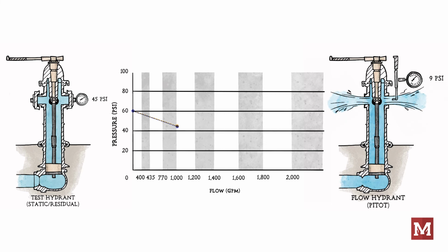Our original curve, we would have estimated fire flow to be about 1,650 GPM. But now, even with a mismeasured residual pressure, our fire flow estimate becomes 1,710 GPM, or just being off by 3.6%. So because we flowed more water, our confidence in our results grows dramatically. Essentially, the real supply that we're going to be able to get out of those hydrants from the fire department is going to be much closer to our test results when we flow more water, when we work our way down that curve.